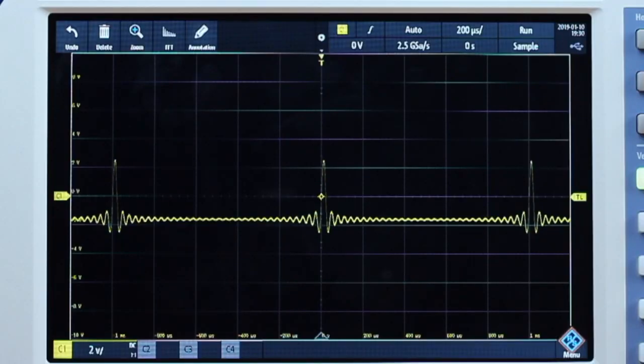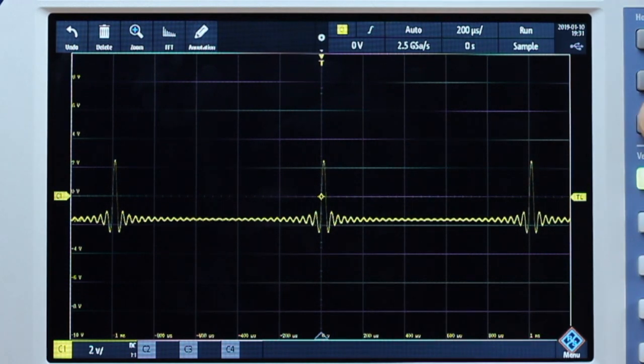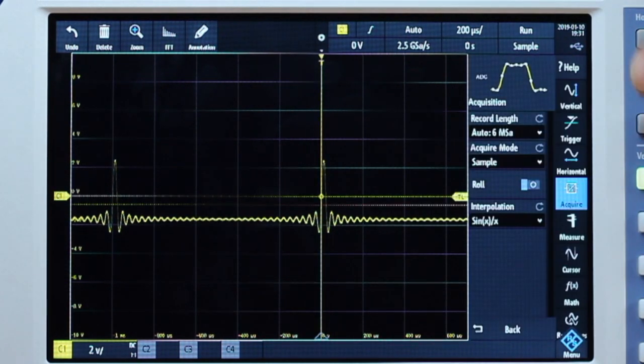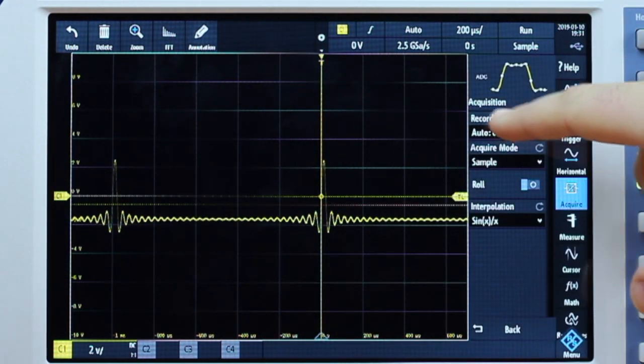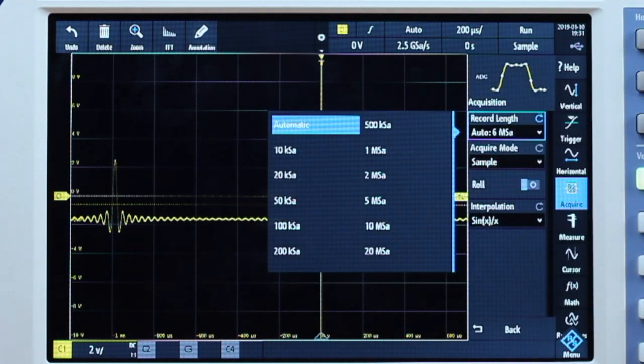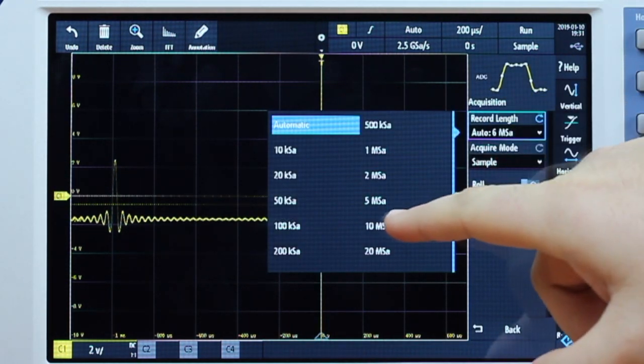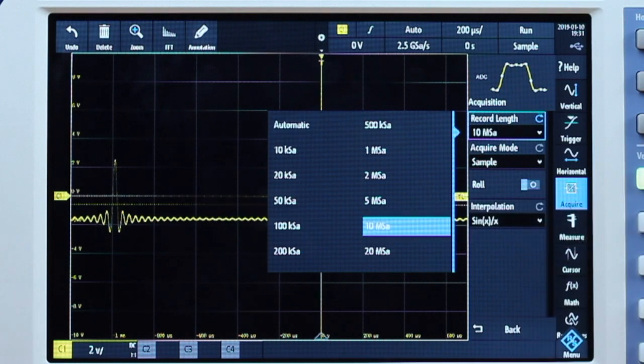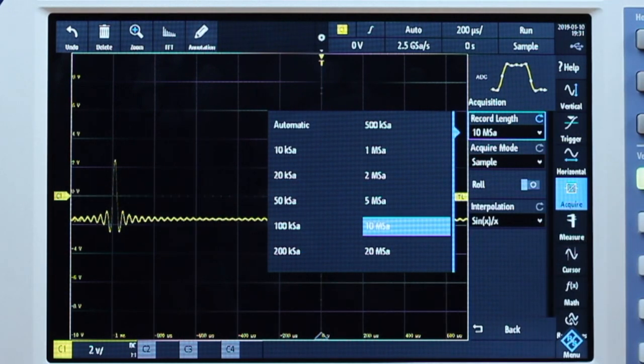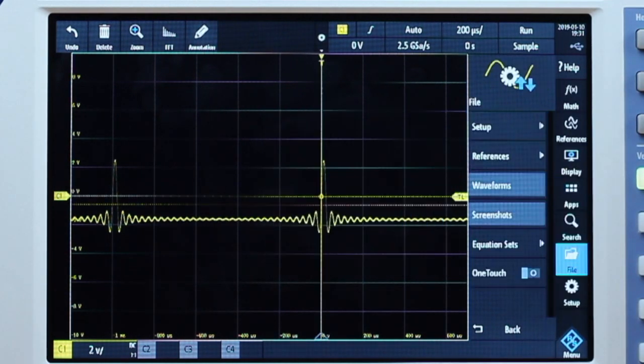Let's begin with capturing a CSV file on the RTB2000 series. To begin, let's go into the acquisition menu and select our record length to be 10 million samples. Once we've done that, we're going to go into our save and load menu.